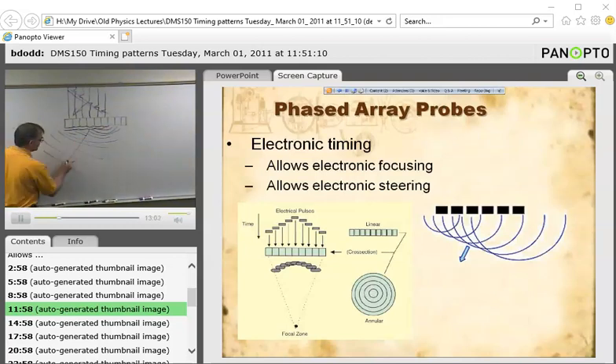And the wavefront is going to be moving in this direction if you have this type of timing on your firing. Okay? So then we can send our wave out this way. We can use reverse timing and send our wave in another direction if we want later. So we could go this way. And we can produce a picture from a standard flat transducer that encompasses a large area that way. Small footprint, large area, by using this electronic steering of the sound waves.